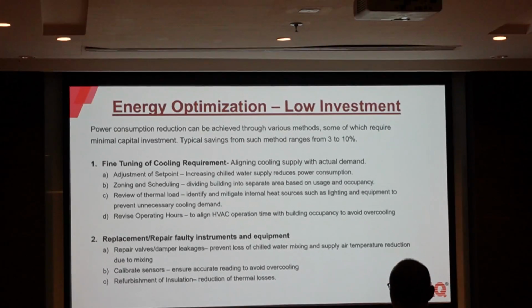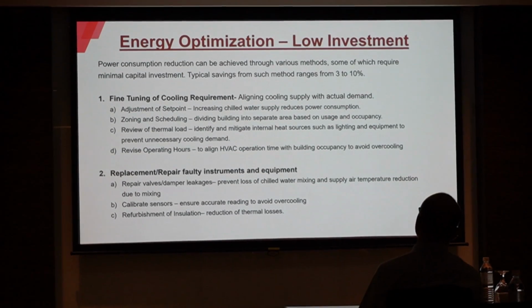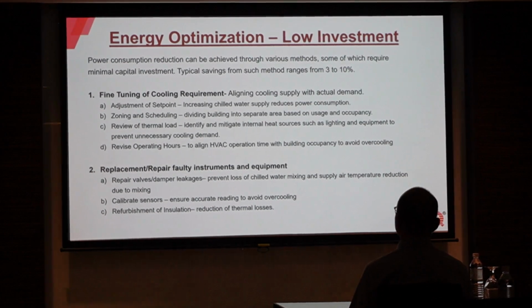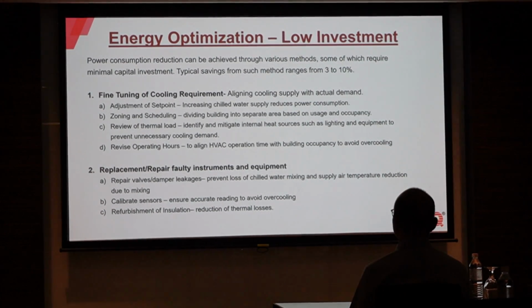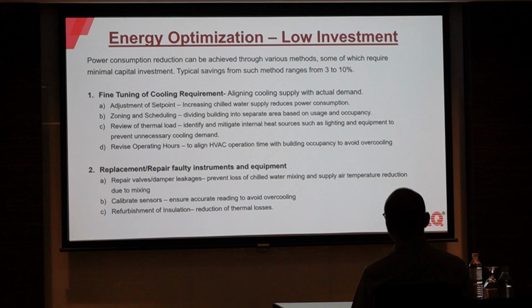Revise operating hours - a lot of operators are also doing this. For example, in a shopping mall or office building, people come in at, let's say, 8 to 5. You can start switching off the aircon a bit earlier, maybe at 4:30, and save an hour a day, or switch it on a bit later. It's purely about changing your aircon operating hours, and from there you get your savings.